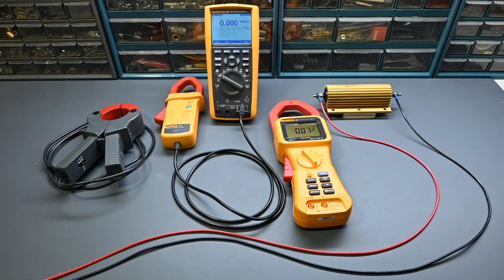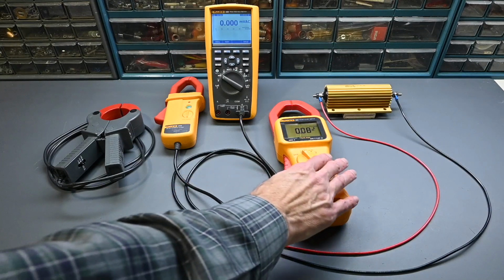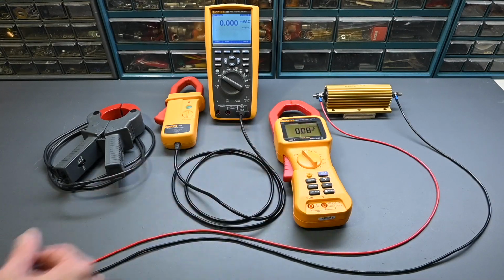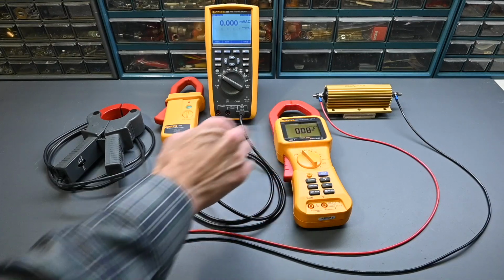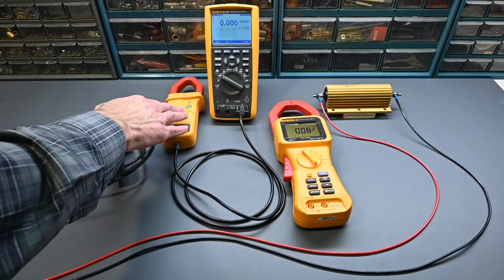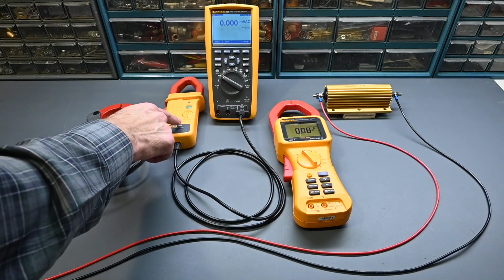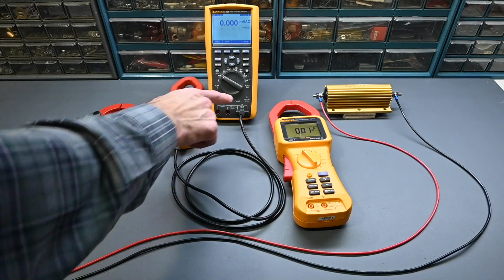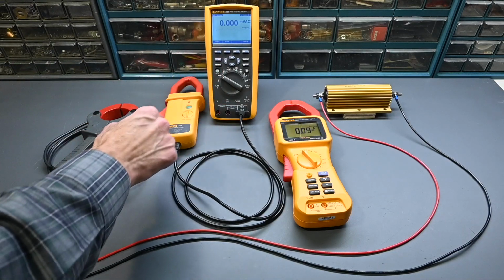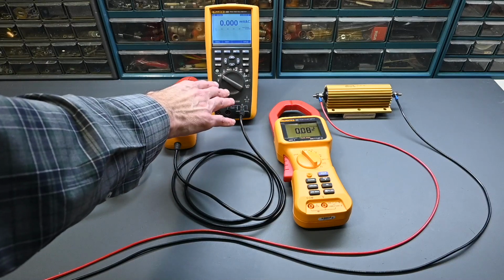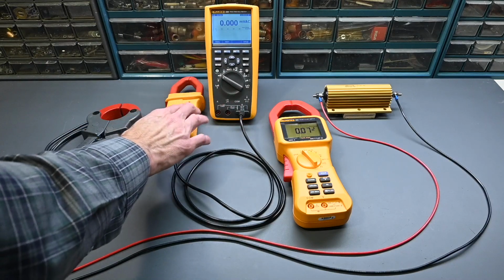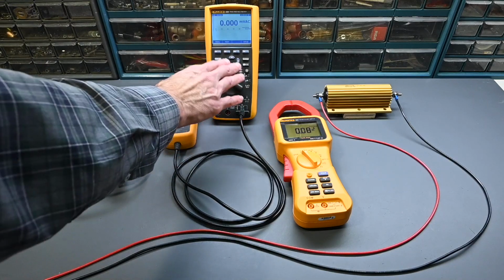Now the accuracy on current clamps is extremely good, but some current clamps require an external digital multimeter if it's not built in. So on this Fluke 355, of course, the display is built in, all self-contained, but for this current clamp and this one, they're going to require an external meter. You can see this one here, the Fluke i410 is plugged into this Fluke 289, so it's requiring an external meter, and the accuracy is going to be the accuracy of the clamp and the accuracy of the meter that you're using.